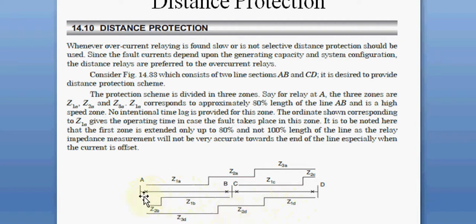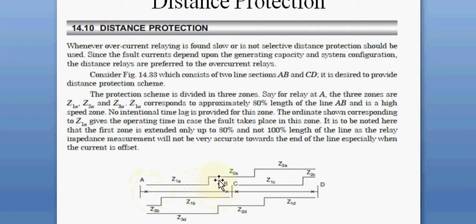For relay A, Zone 1 covers 80% of the length of line AB. Zone 2 of relay A covers the remaining 20% of line AB and also covers an extra 20% or 50% of the adjoining line.